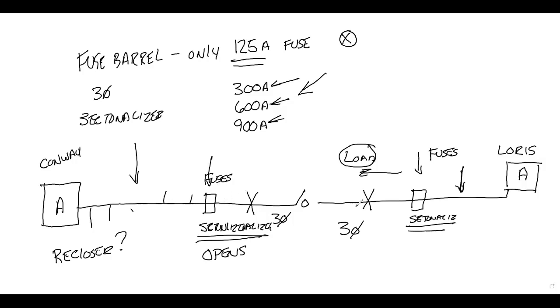Some sectionalizers can also be hooked up to SCADA for remote operation, so you get an indication of where the fault is. Instead of sending a guy out in a pickup truck to drive five miles, the sectionalizer tells you the fault is beyond it, narrowing your patrol area to two and a half miles. When the sectionalizer opens, the breaker and all customers prior to the sectionalizer remain on.